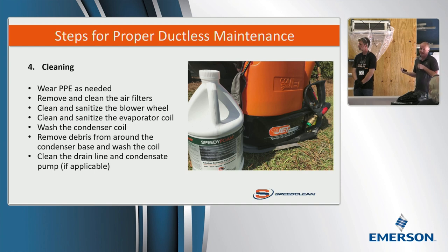This is just a good practice anyway, because you've got your compressor in there, you've got everything in there, and if debris is starting to build up and water is starting to get in there, you're going to begin to get corrosion. In these units, everything is really close together, so you want to prevent stuff from getting in there in the first place. And then clean the drain line and the condensate pump, if applicable. Cleaning the condensate pump, the reservoir, the screen, all of that is one of the biggest things I see get missed. So if you got one, you got to clean it.